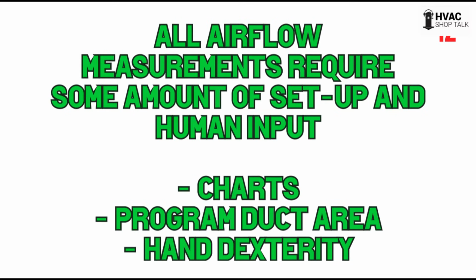All these devices, like vane and hot wire, you have to put in what kind of duct you have if you want to calculate the CFM. You don't want to put in the wrong duct. You want to make sure you measure it correctly, not just say it looks like 12-inch round. You want to measure it correctly because it makes a big difference to what you're getting out.